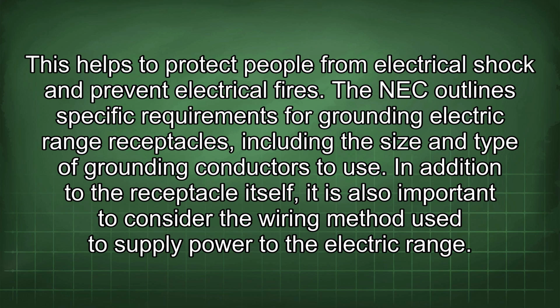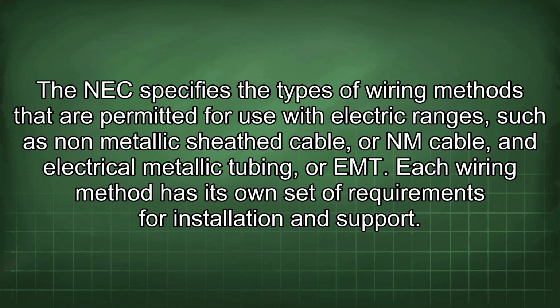In addition to the receptacle itself, it is also important to consider the wiring method used to supply power to the electric range. The NEC specifies the types of wiring methods that are permitted for use with electric ranges, such as non-metallic sheathed cable or NM cable, and electrical metallic tubing or EMT. Each wiring method has its own set of requirements for installation and support.